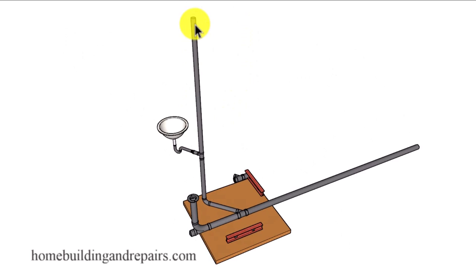This part of the fitting will be level and go out the top of the roof and can be plumb or vertical. This section of the pipe, wherever I'm referring to as horizontal, will need to slope towards the sewer or septic tank. And this will depend upon the pipe size. Could be anywhere from an eighth of an inch to a quarter of an inch minimum slope per foot.